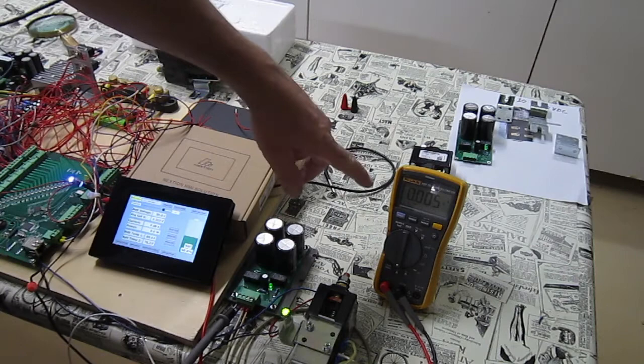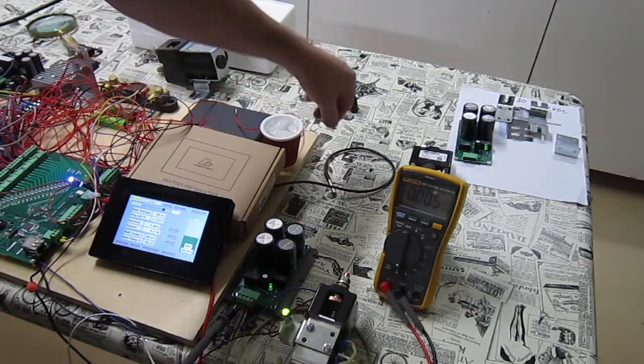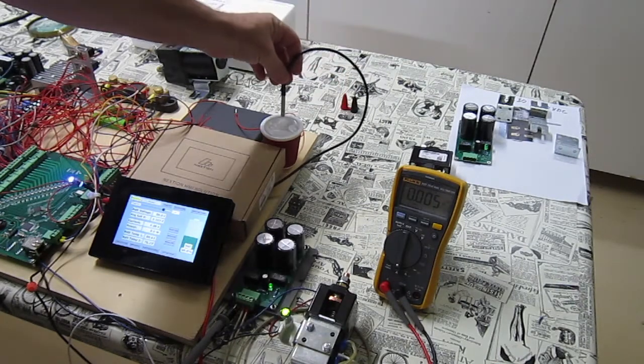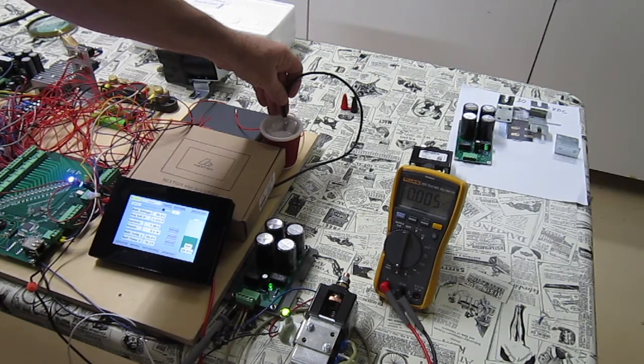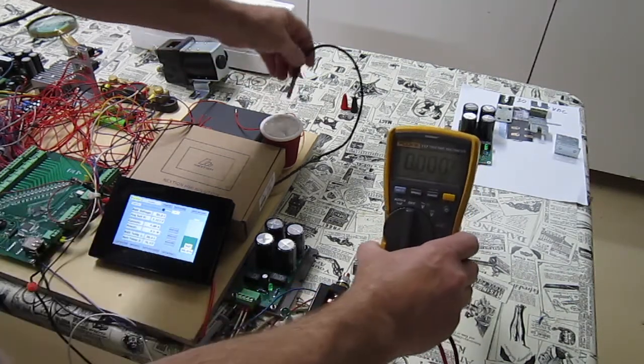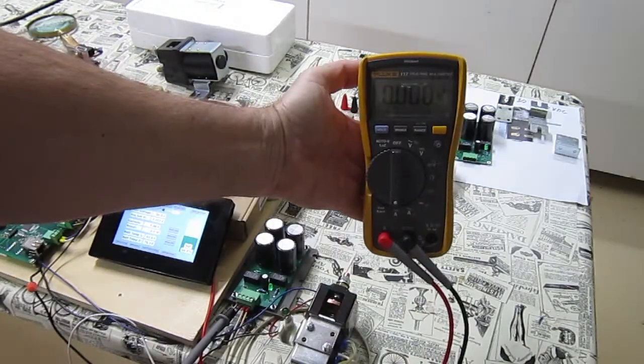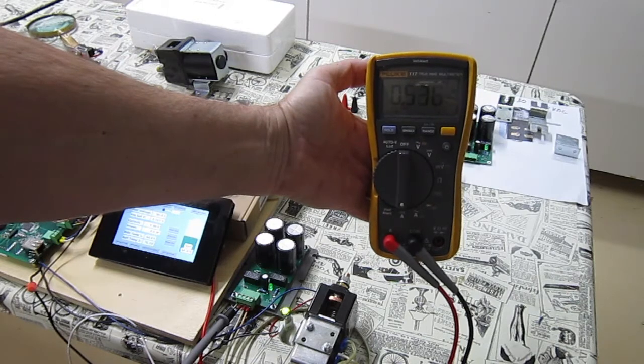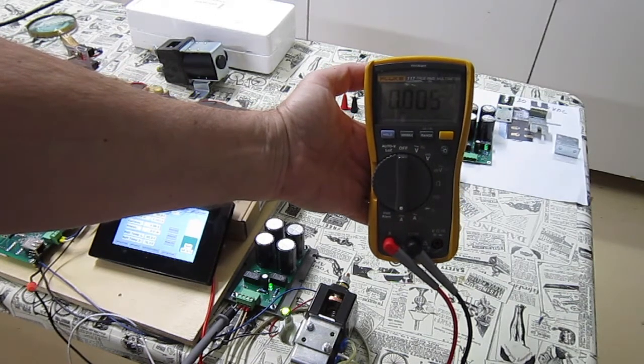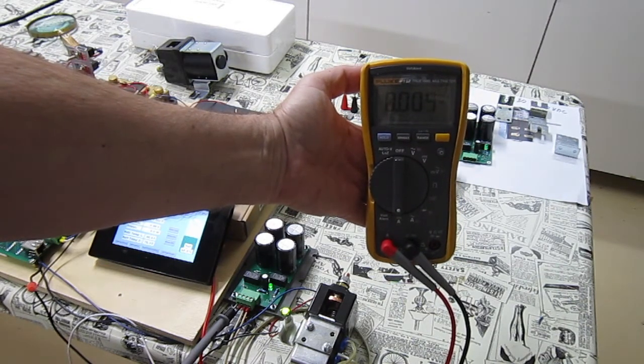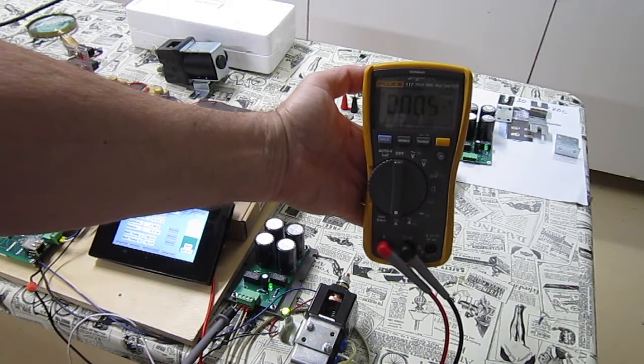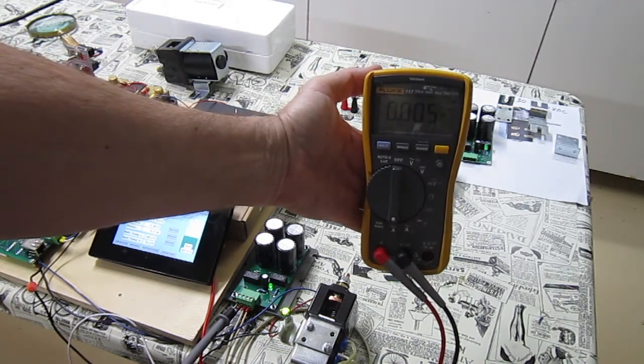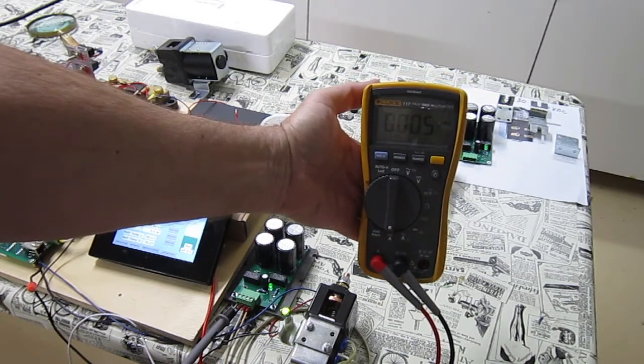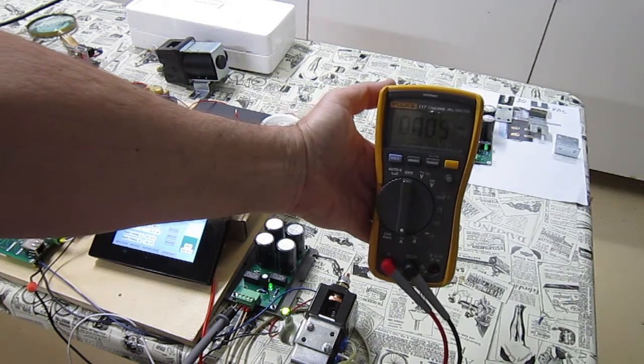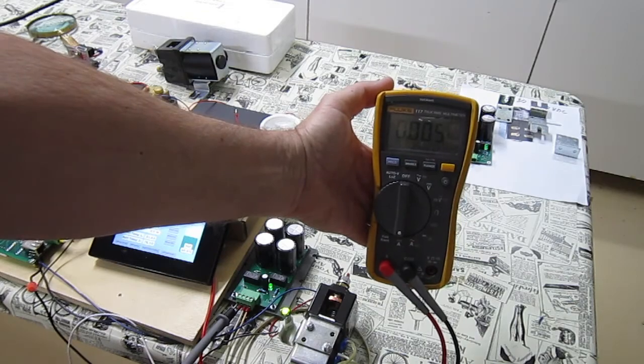This is the standby load. It's 5 milliamps. Let's cycle it, see if we can capture the inrush. So that's not bad. 4 to 5 milliamp standby load as compared to 340 for a 400 amp standard contactor and about 115 milliamps for that 200 amp contactor that I'm using now.